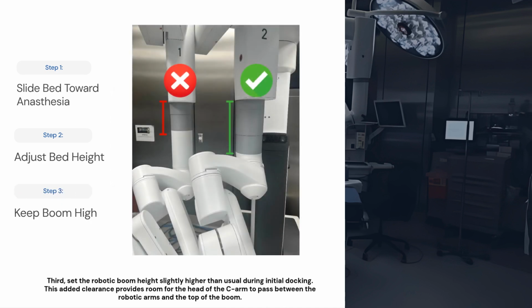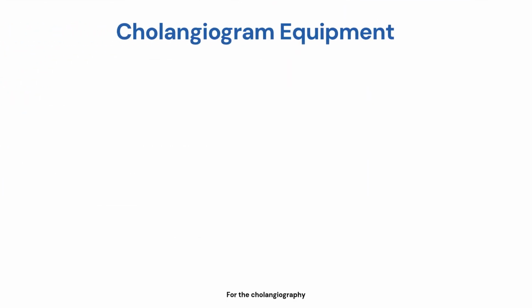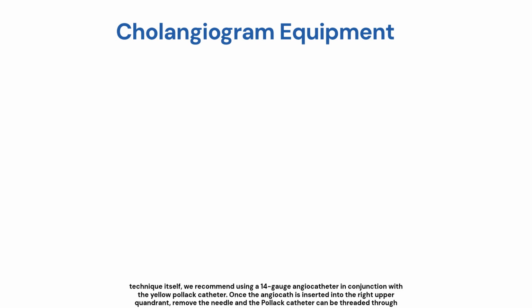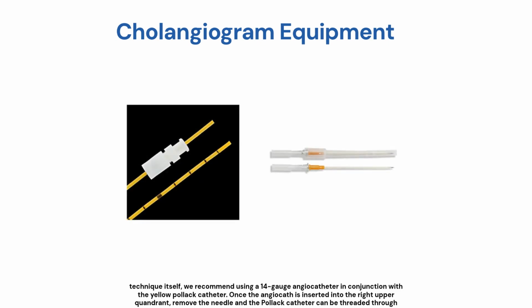Third, set the robotic boom height slightly higher than usual during initial docking. This added clearance provides room for the head of the C-arm to pass between the robotic arms and the top of the boom.